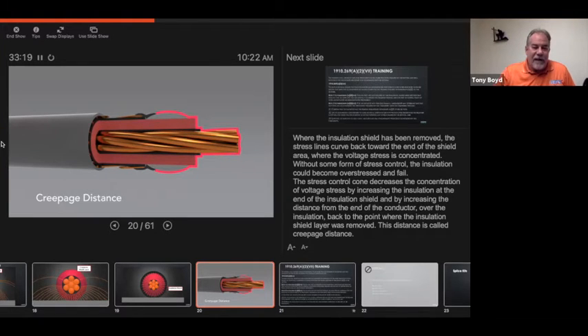Let me see if I can get my arrow back over there to it. And that's basically what this is showing, is a stress cone. So it allows us some extra insulation for that stress that is coming up and trying to go back over it and get to ground. So here, all the stress lines are even. Here, they're going to concentrate because there is no more semiconductor shield. So that's why this part of an elbow or a terminator or a splice kit is so important.